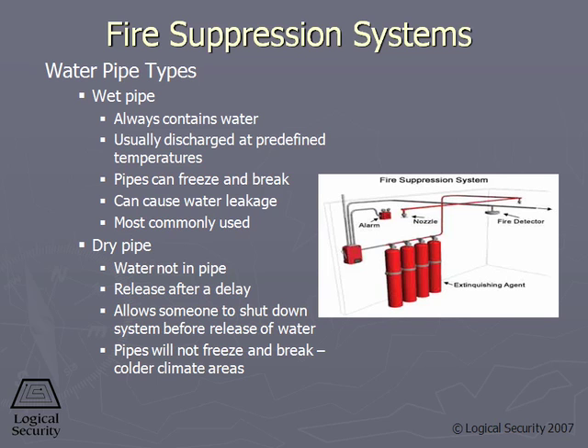The problem with the dry pipe, though, is there is a delay in the time that the alarm sounds, then the valve opens, we now have to fill the pipe, and that's when the sprinkler heads finally release the water. So the dry pipe protects against frozen pipes, but has a built-in delay from the time an alarm sounds until the water actually starts to penetrate the area where we're trying to put out the fire.